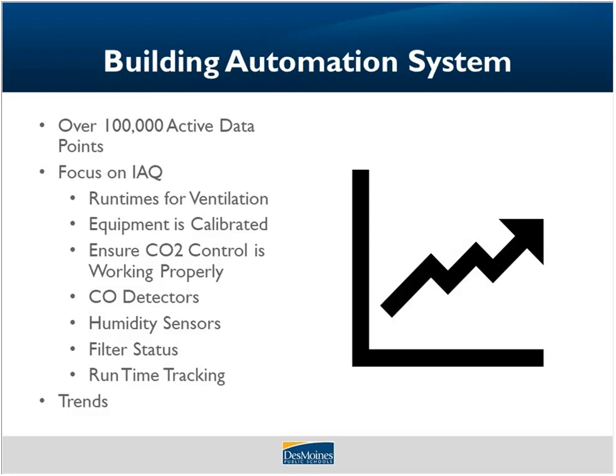We also use demand-based ventilation to control the amount of outdoor air that's introduced to our spaces. This uses CO2 sensors placed within building spaces and the HVAC units in order to determine which spaces need additional ventilation. We've also experimented with people counters in large conference rooms and cafeteria type spaces. These work by counting the number of people through a doorway and increasing or decreasing the ventilation rate depending on the number of people. These seem to work well, but access to that area can be controlled through 1 or 2 doorways.